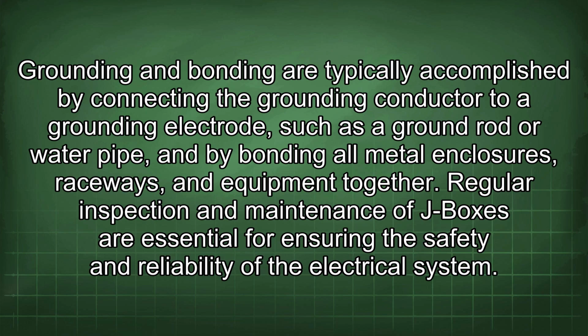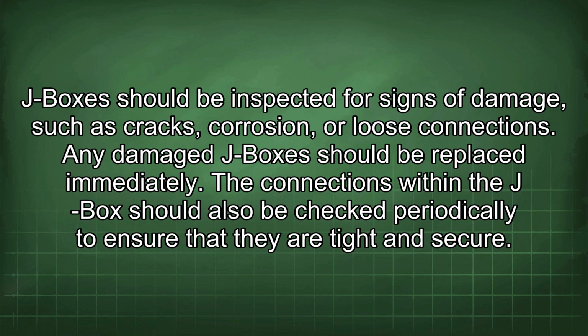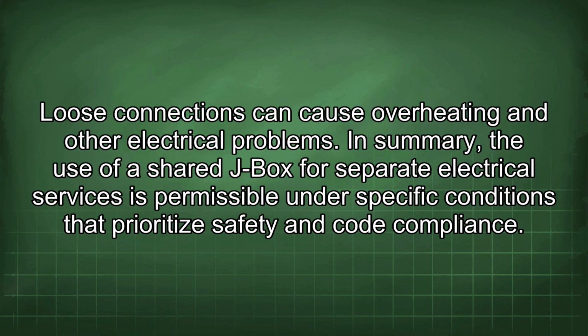Regular inspection and maintenance of J-boxes are essential for ensuring the safety and reliability of the electrical system. J-boxes should be inspected for signs of damage such as cracks, corrosion, or loose connections. Any damaged J-boxes should be replaced immediately. The connections within the J-box should also be checked periodically to ensure that they are tight and secure. Loose connections can cause overheating and other electrical problems.